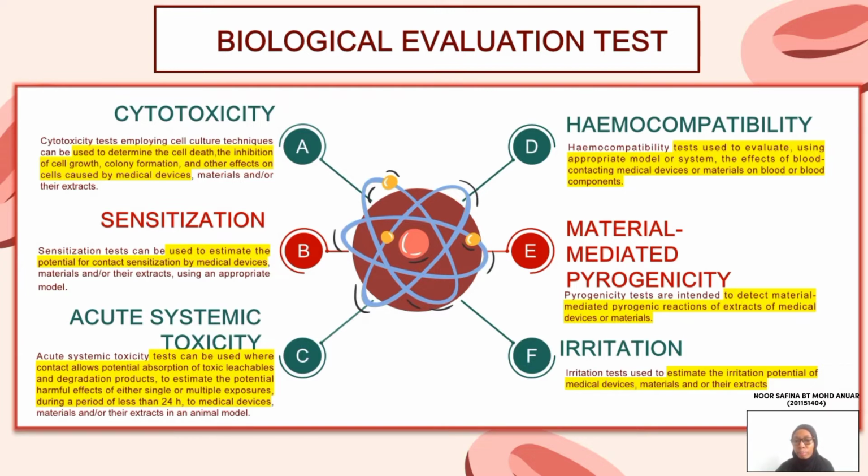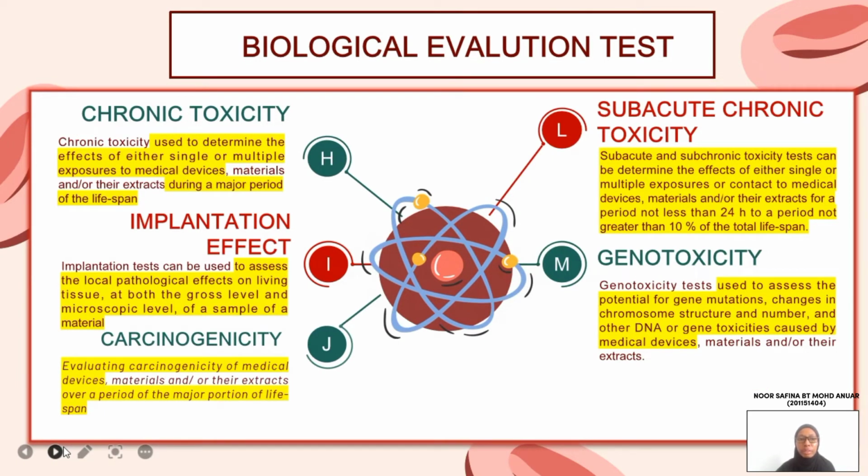For material-mediated pyrogenicity, these tests are intended to detect material-mediated pyrogenic reactions of extracts of medical devices or materials. Irritation tests are used to estimate the irritation potential of medical devices, materials, and/or their extracts.